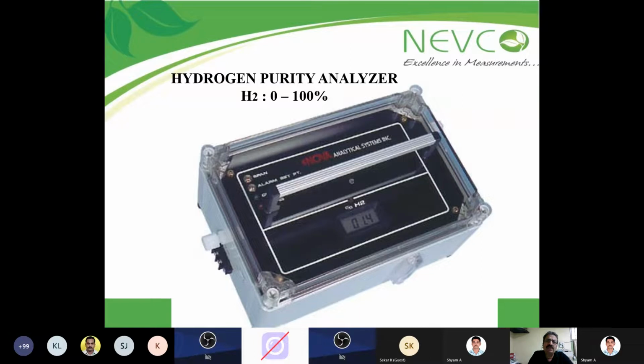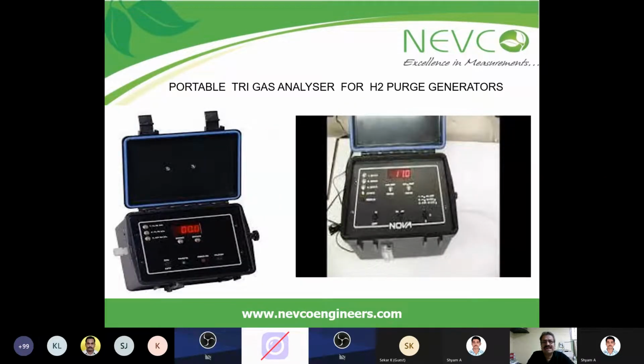Then we have a hydrogen purity analyzer. It has a lot of use, up to 100% hydrogen. Then we have a portable tri-gas analyzer for hydrogen purge generators and for different R&D applications. This has a lot of uses, very specifically in high capacity power plants where the generators are being purged with pure hydrogen. If the purity of hydrogen comes down, then it will cause a problem with the generator. So you have to always ensure that the hydrogen you are purging for cooling has more than 99% purity. If it is below 99% purity, it will not work properly. It has to be checked every time. To check that, these tri-gas analyzers are mostly used for power plant applications.